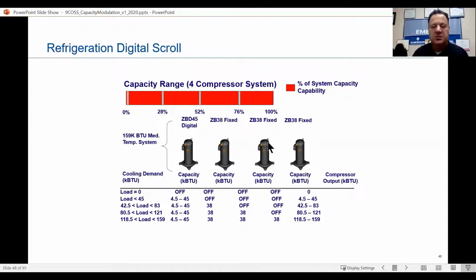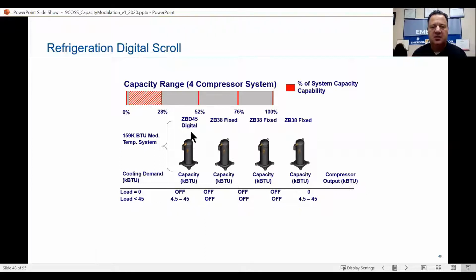Now, as the store starts to empty out and the sun starts to come down and we start to cool off the store, the same thing happens. It's going to start coming down. You can see, again, load matching. Keeps going back to the load matching. Every time it drops off a digital or a fixed compressor, pardon me, it load matches that digital. The digital loads down, then ramps up as it's needed until it's completely shut off. Again, back to zero, all the compressors are off.